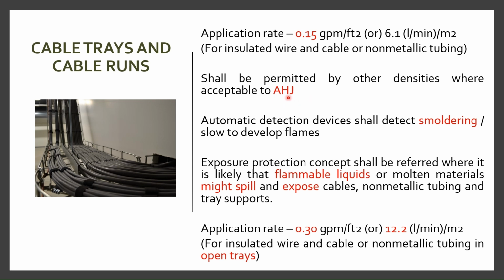If you want to bypass NFPA 15, you need to have approval from the AHJ, and automatic detection devices shall detect smoldering or slow-to-develop flames, because in cable trays, especially through the cables, there will be slow-growing fires, wires short, or things increasing very slowly. We cannot identify those. Because of that, we need to provide automatic detection devices to catch the slow-developed flames as well.